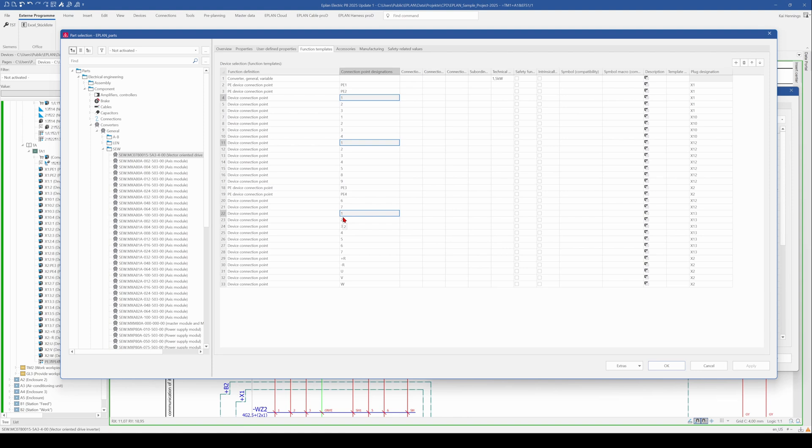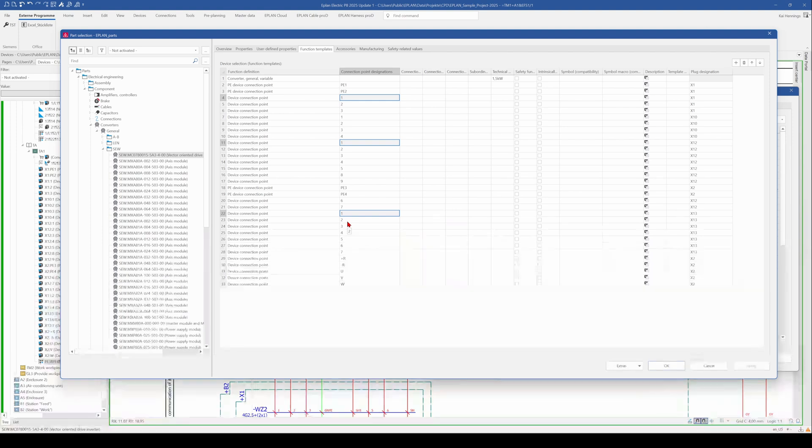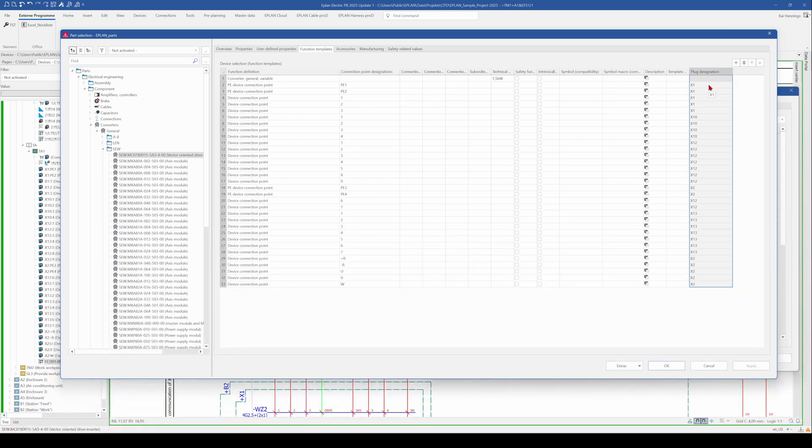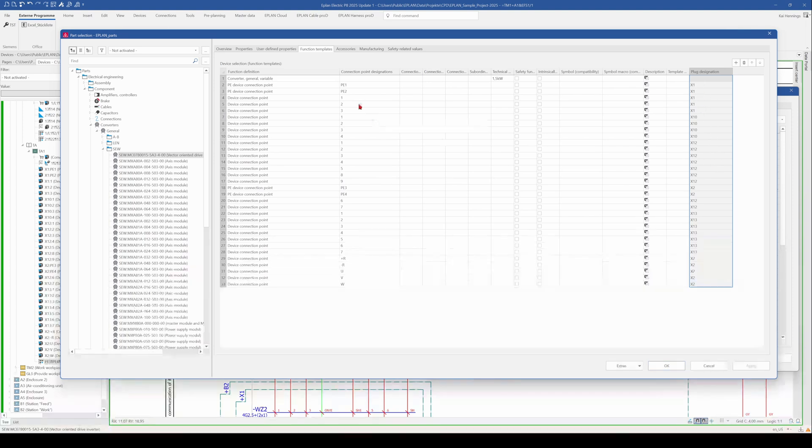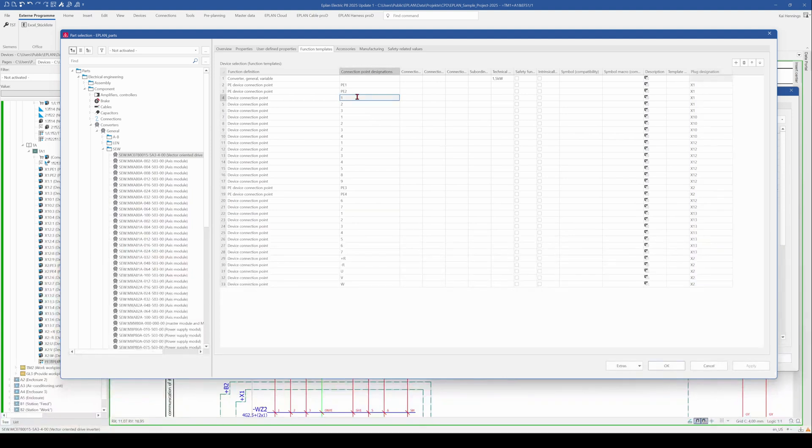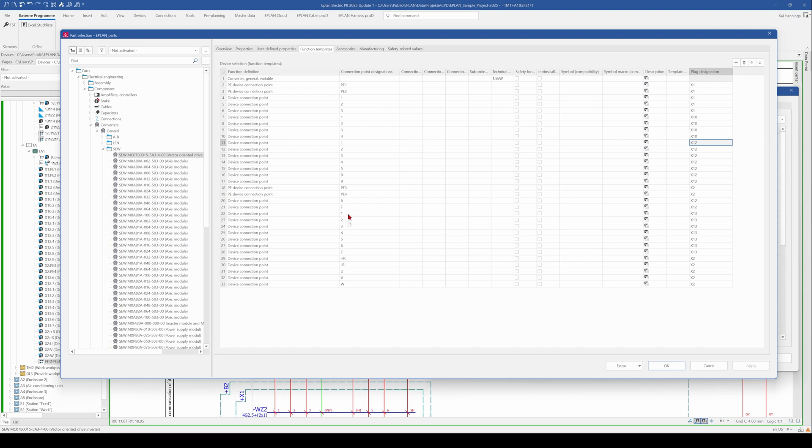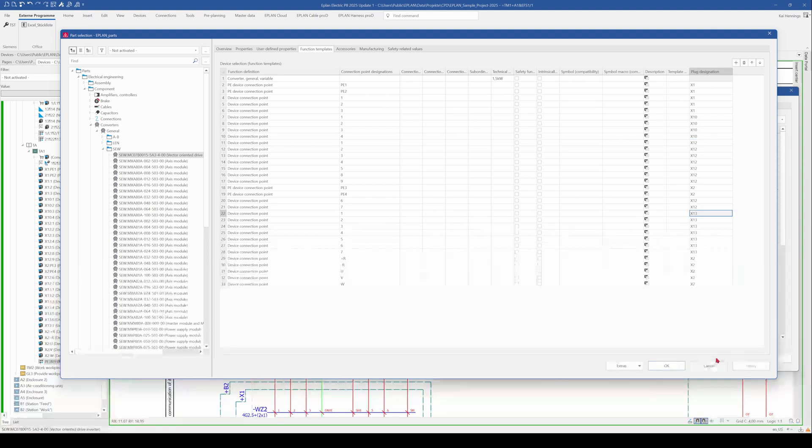And makes it impossible for routing of the wire, for example, to find the right position if you have not an additional designation. And therefore we have here the plug designation. And here is the plug designation. And that means when you add it here, it's a unique connection point here. This is X1, 1 and here you have X12, 1 and here you have X31. So this is the right way how it works.